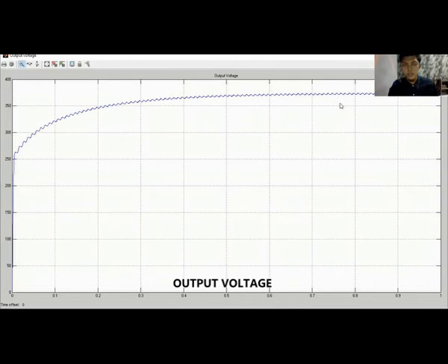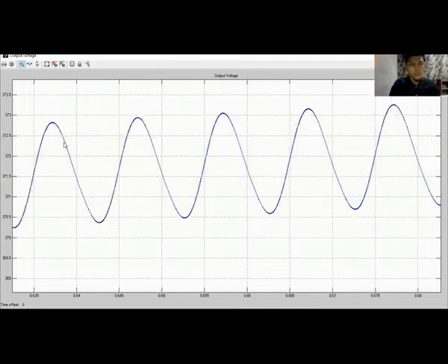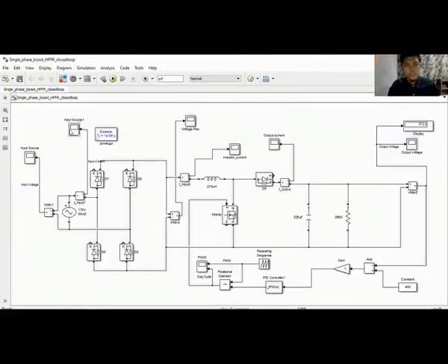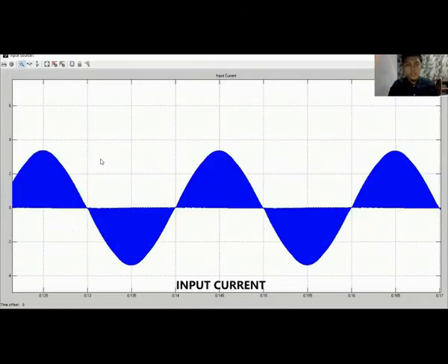This is the voltage produced by the closed loop AC-DC discontinuous boost converter, and we can see that the ripple voltage is much lower than the open loop without the PFC, an estimated 2.5 to 3 volts of ripple voltage difference produced. The input current is expected to be sinusoidal. The input current produced by the closed loop is a sinusoidal waveform, which follows the input voltage from the supply. So this is a good result from our closed loop using the PID controller with the power factor correction.